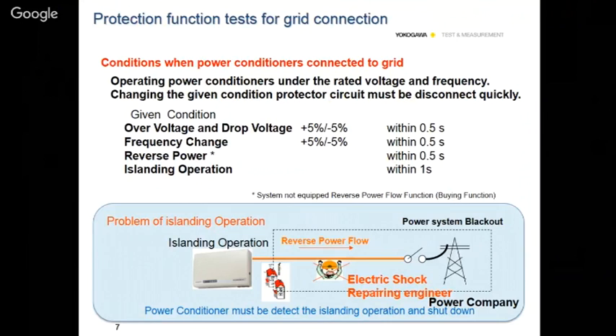So that means we are talking about switching. How do we ensure that it is happening within that 0.5 second, or 500 milliseconds? That is where the oscilloscope or the scope recorder comes into the picture. For example, in a grid, we connect the protection circuit and, in parallel, we hook up the DL850. We connect it and leave it, and we set an N trigger function. For example, in a day maybe 10 or 20 events can occur, so I set the N trigger function and leave it.